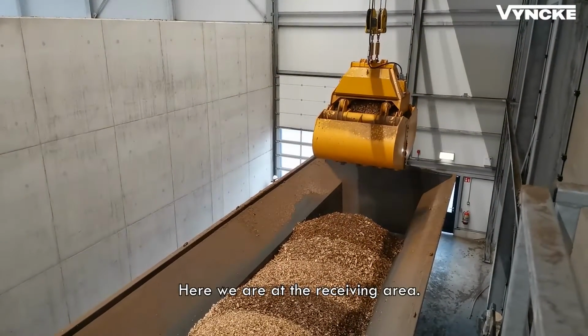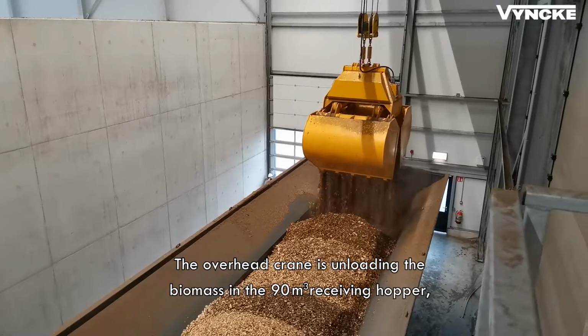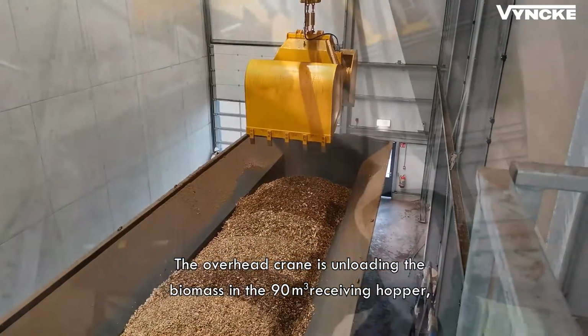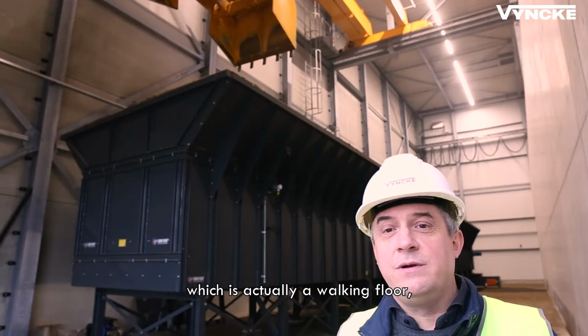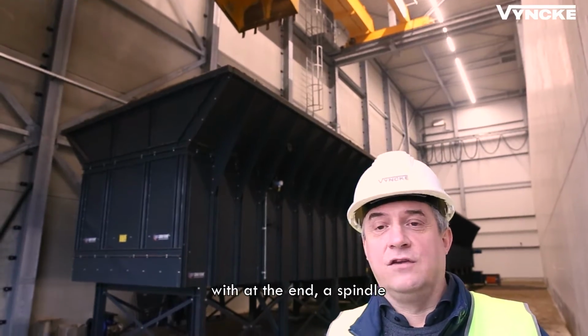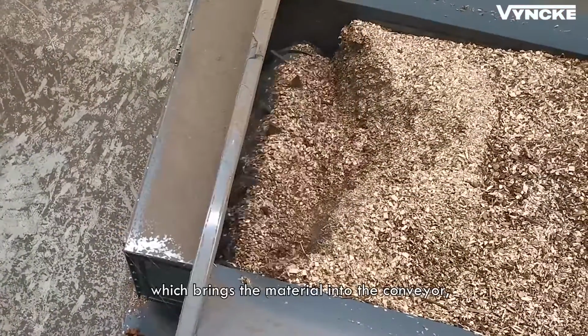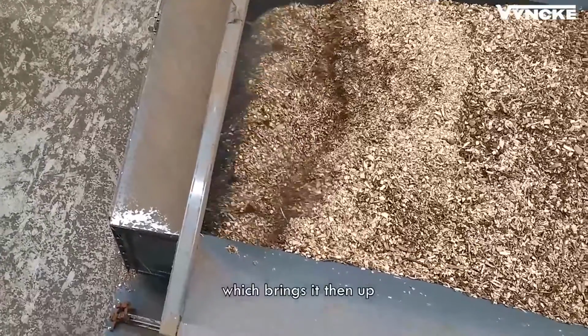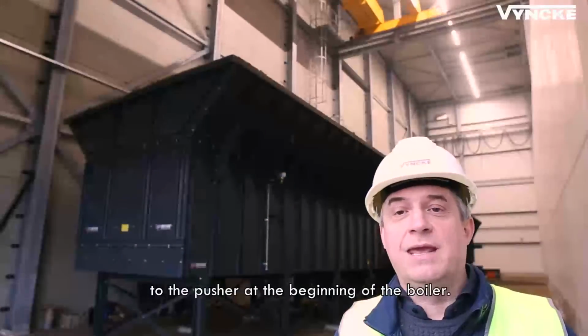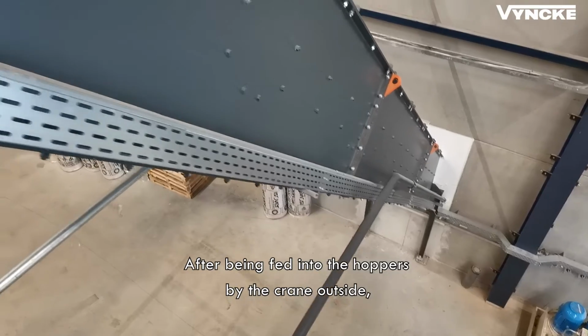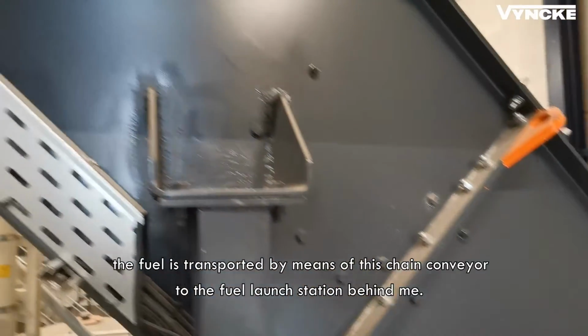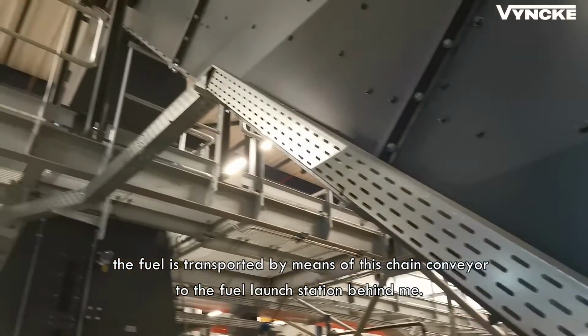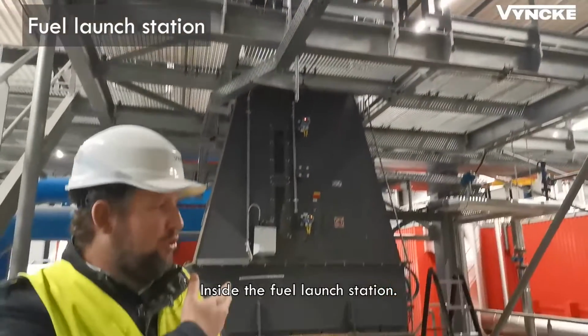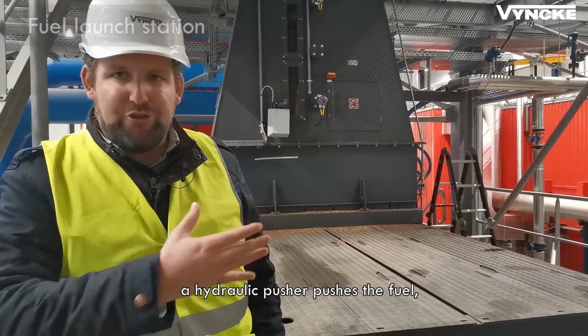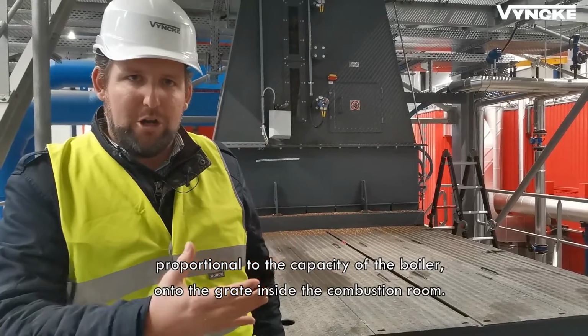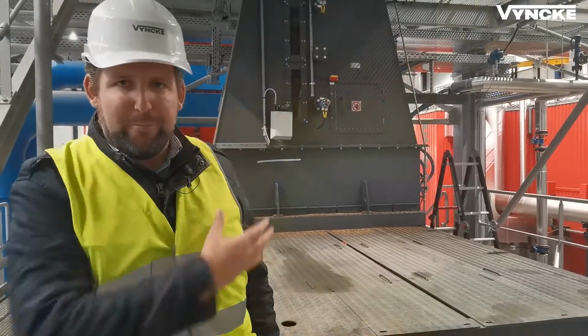Here we are at the receiving area. The overhead crane is unloading the biomass in the 90 cube receiving hopper, which is actually a walking floor with at the end a spindle which brings the material into the conveyor, which brings it then up to the pusher at the beginning of the boiler. After being fed into the hoppers by the crane outside, the fuel is transported by means of this chain conveyor to the fuel launch station behind me. Inside the fuel launch station, a hydraulic pusher pushes the fuel, proportional to the capacity of the boiler, onto the grate inside the combustion room.